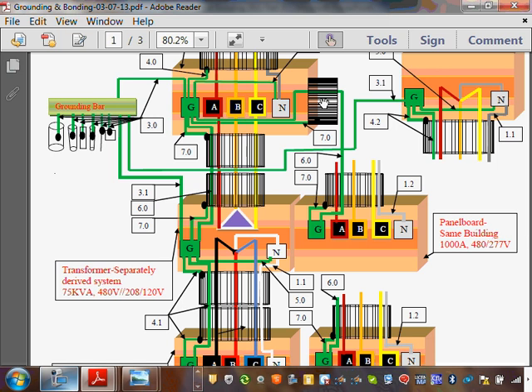You get rid of all the knockouts, and you have a 1/2 inch hole with a 1/2 inch conduit with no eccentric or concentric knockouts. Your lock nuts will get you the bonding for EMT or rigid, or intermediate; PVC is not. On the 480, if you have a knockout for 1/2 inch EMT conduit, say, but it's highly unlikely with these, into a 480/277 panel, you still have the eccentric or concentric, then you cannot use the lock nuts. You have to use bonding bushings.